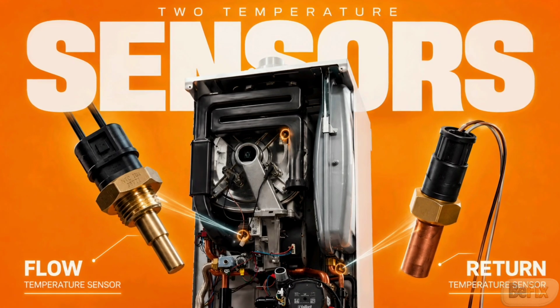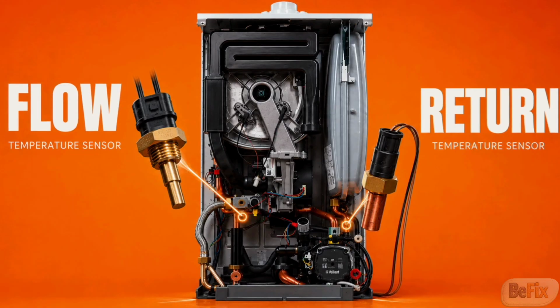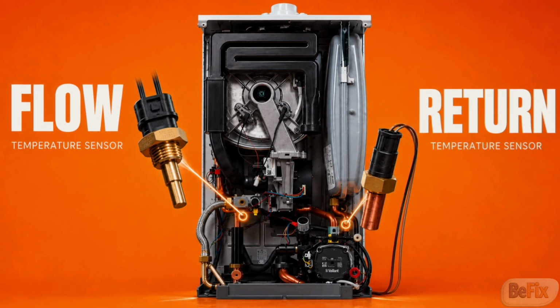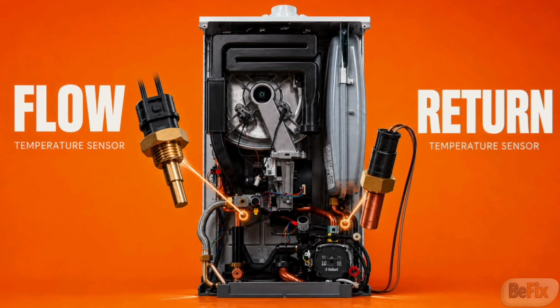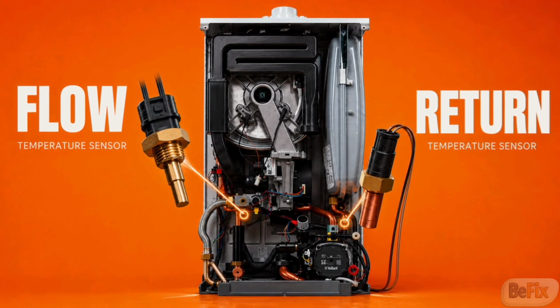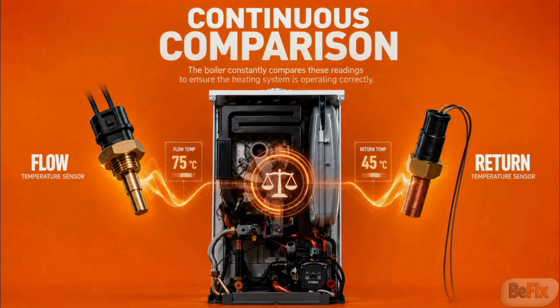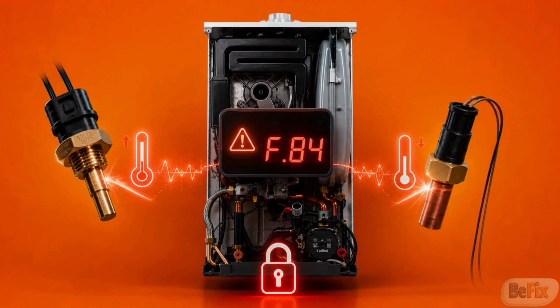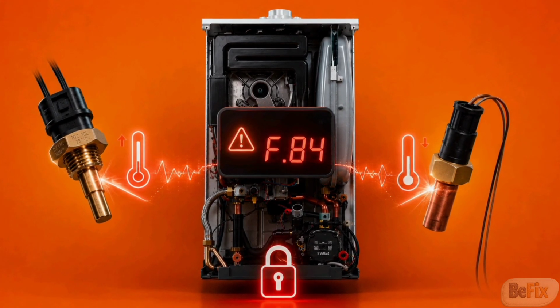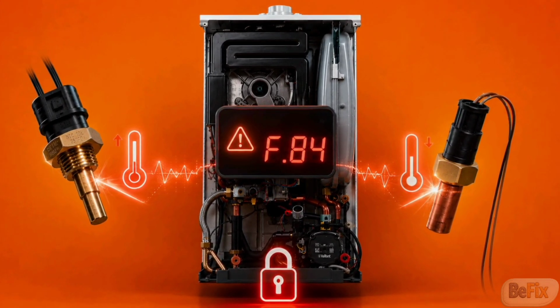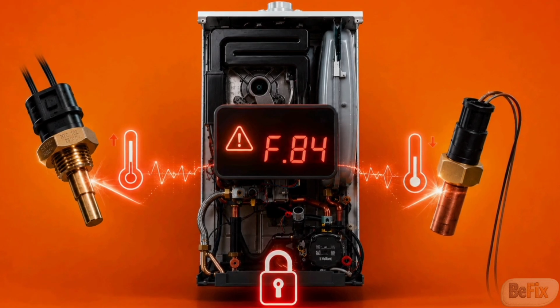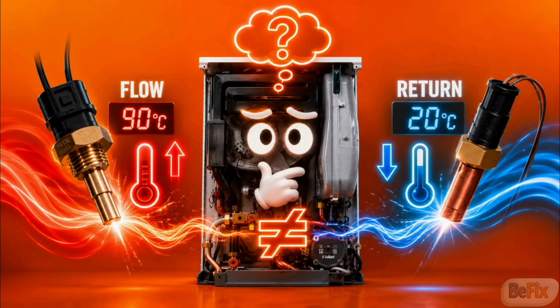Inside your boiler are two temperature sensors. One measures the temperature of the water leaving the boiler, known as the flow temperature, and the other measures the temperature of the water returning to the boiler. The boiler constantly compares these readings to ensure the heating system is operating correctly. If the readings become unrealistic or don't match what the boiler expects, it will lock out and display an F.84 fault code. In simple terms, the boiler believes the flow and return temperatures are incorrect or inconsistent.